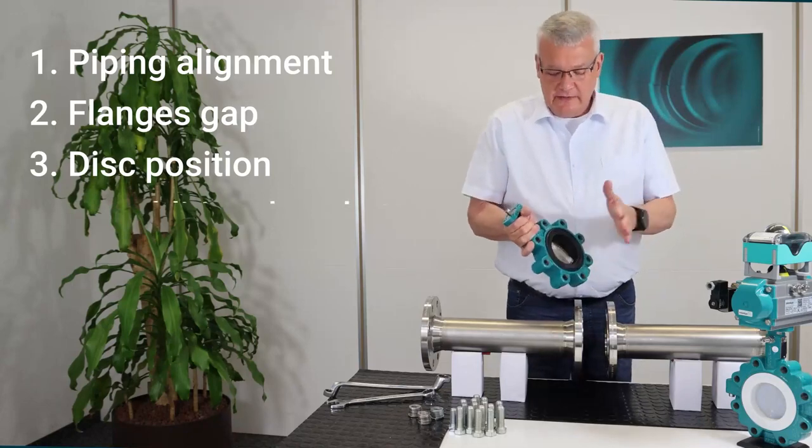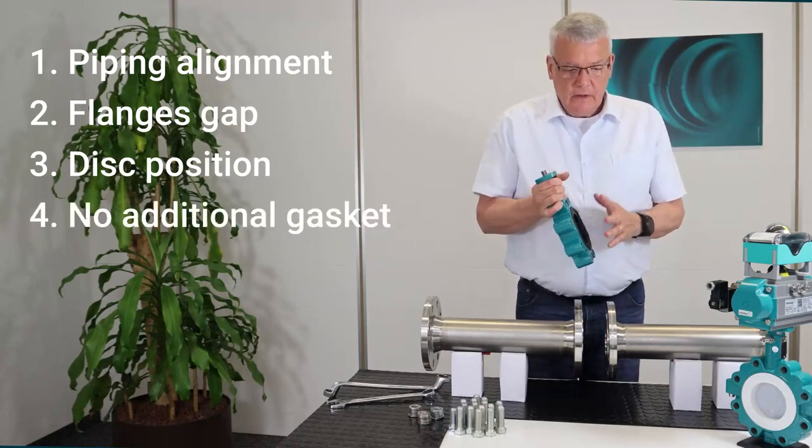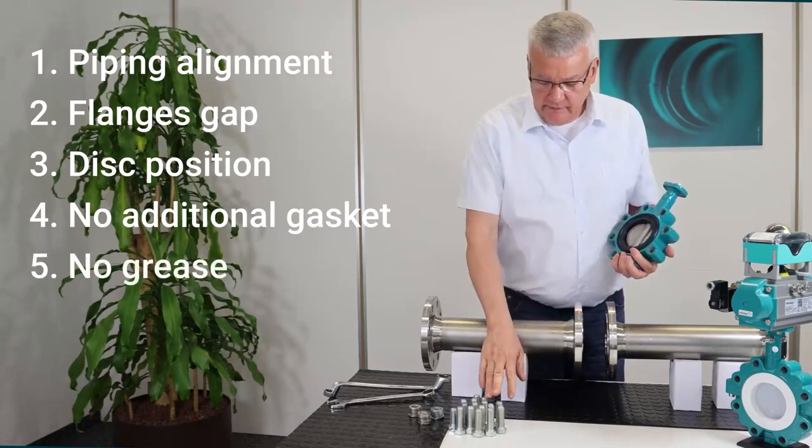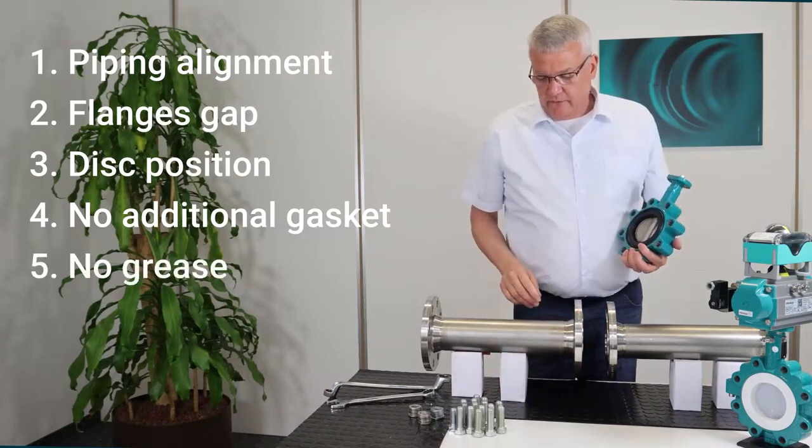You should never use additional gaskets. You should not use grease except the grease you need on the screws of the flanges.